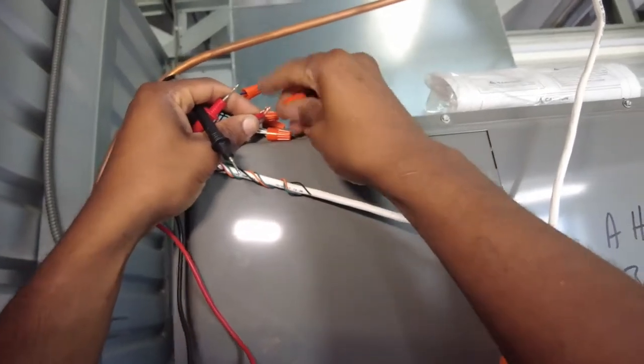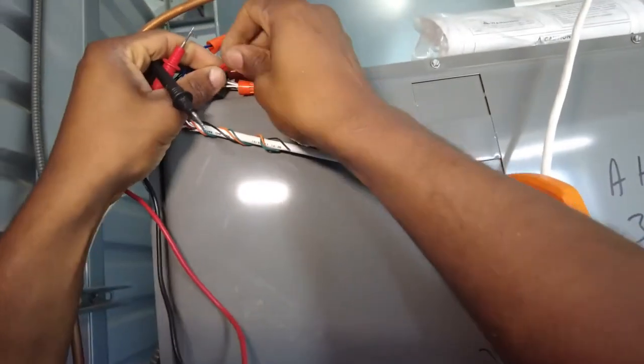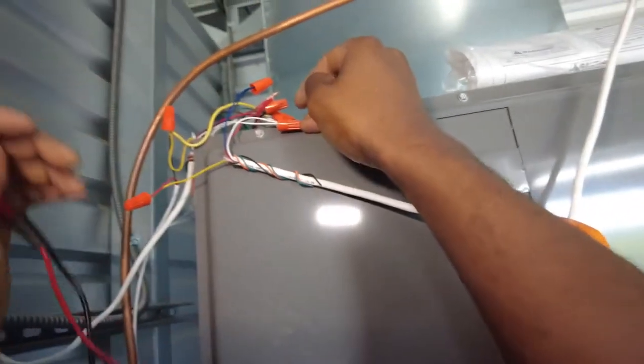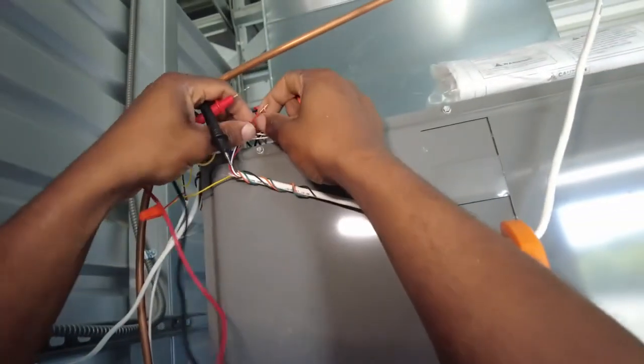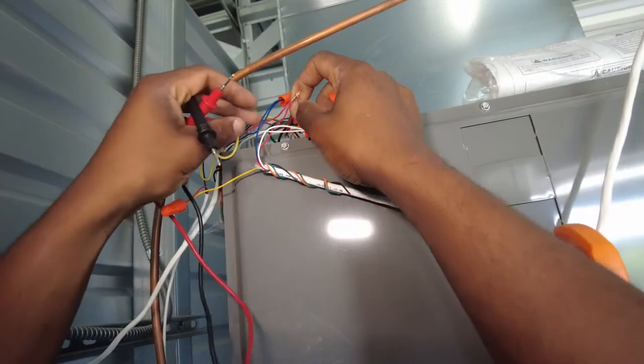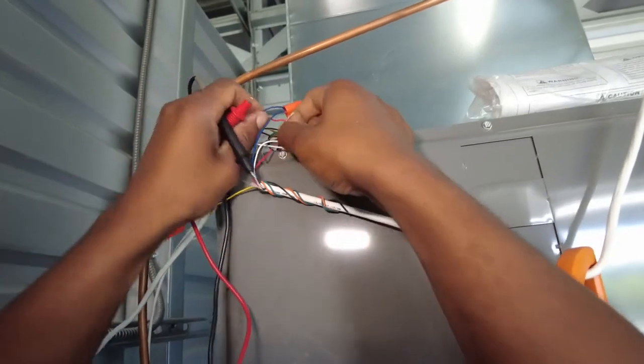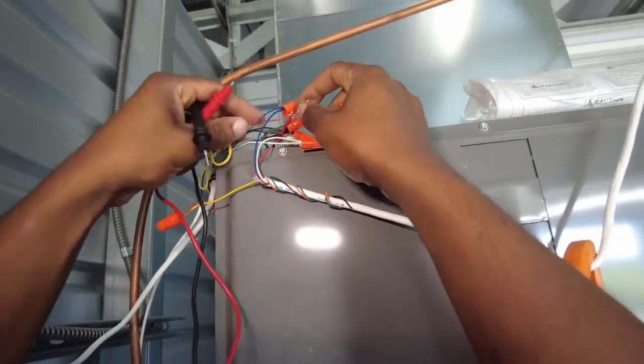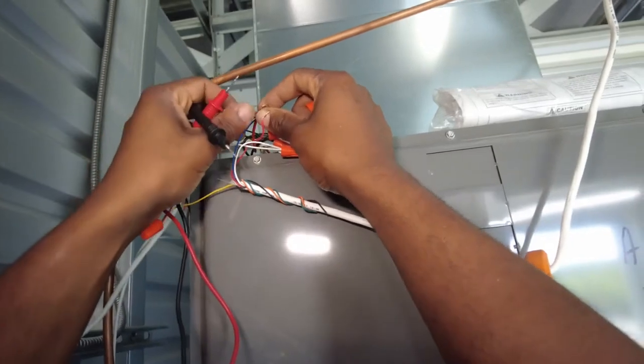24, but we're seeming to be getting a drop somewhere. Let's see. Let's see if I take, it's coming from the thermostat. Let's take the outdoor unit out of the circuit.